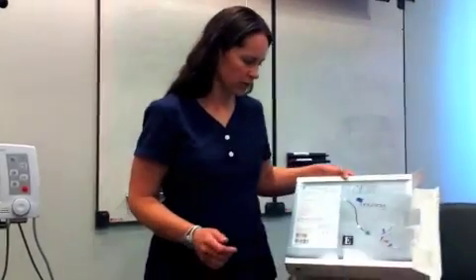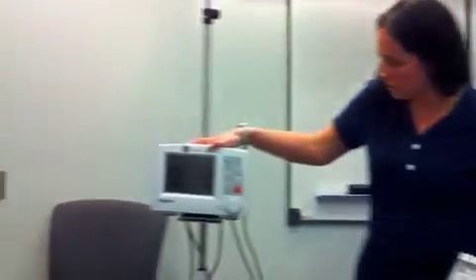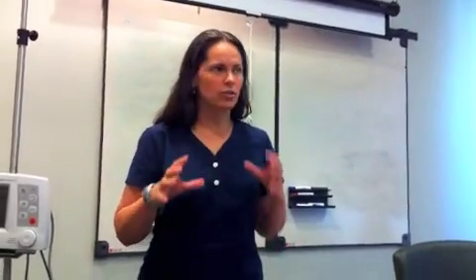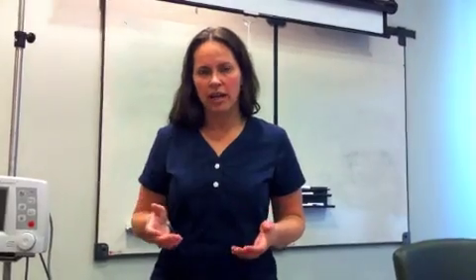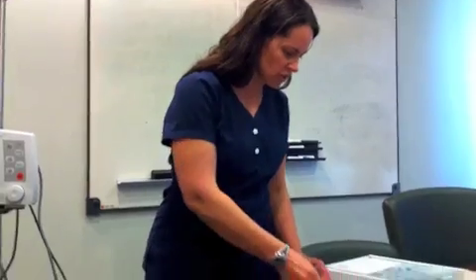It does require this box, so what you'll need is this and your machine. It's best to wait until the physician inserts the PreSep catheter before you try to calibrate, so that we do in vivo. Trying to do things in vitro gets complicated and you have to calibrate it again. So wait until the physician inserts the catheter.